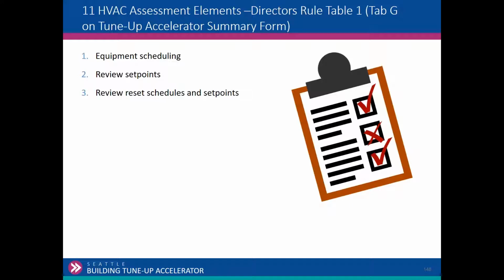We're not asking you to develop new sequences of operation. I've had people ask me, well, I need the commissioning report, and then I can functionally test per the commissioning report. You don't need that. Is the equipment performing per standard practice? If you've got those commissioning reports and you can at least have a baseline to compare your tune-up to, great. But that's not necessary. You don't need an OPR. You don't need sequences. Is optimum start-stop applicable? We'll go through this.